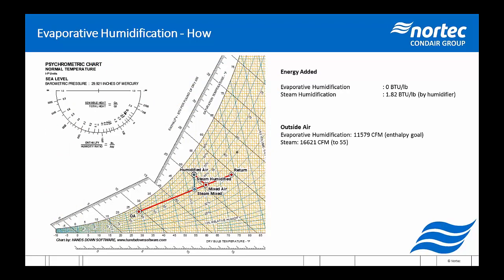This is a situation in which the energy put into a steam system is, again, you need to boil it. So you've mixed your air side economizer to about 55 degrees, which means you've pulled in around 16,000 CFM. The number's not that important. You've pulled in more outside air than if you're humidifying with an evaporative humidifier. With an evaporative humidifier, you actually mix to an enthalpy set point. And at that point, your mixed air temperature is around 61 degrees, and you can just humidify evaporatively, again using zero energy, as opposed to the 1.8 BTUs per pound that a steam humidifier would have to put in.